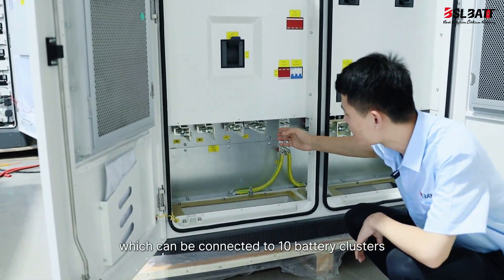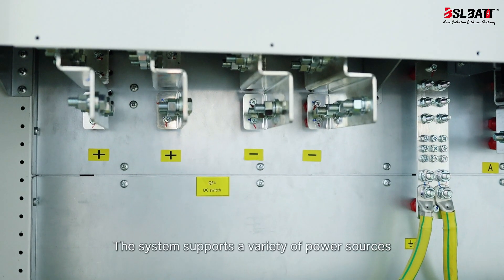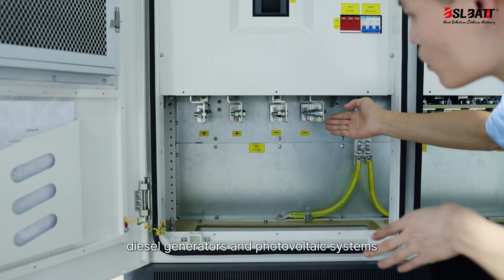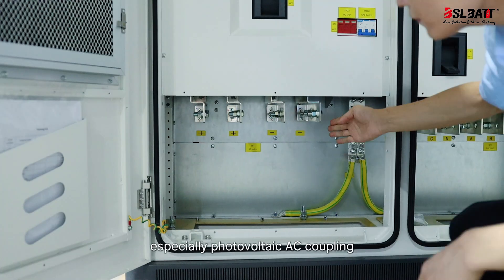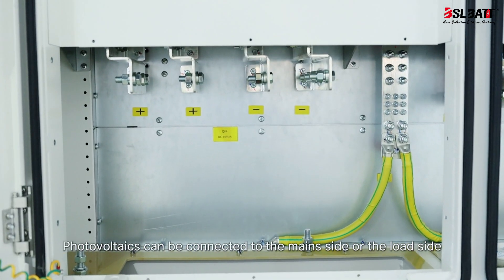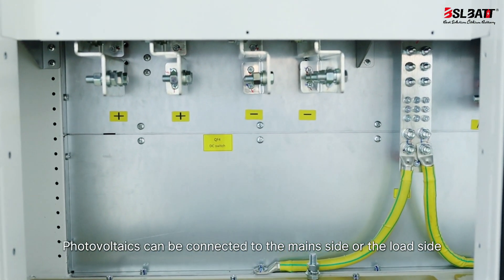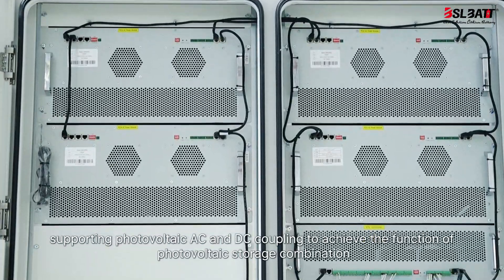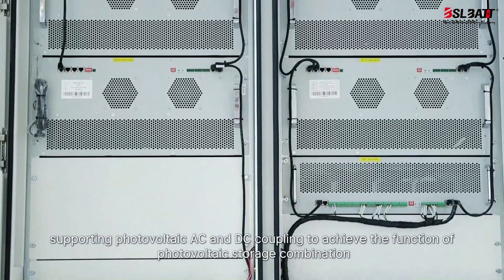The STS module in the cabinet has a power of 600 kW. Compared with the traditional ATS, it can switch on and off the grid faster. The PCS cabinet also integrates the function of the combiner box, which can be connected to 10 battery clusters. The system supports a variety of power sources including mains, diesel generators, and photovoltaic systems, especially photovoltaic AC coupling. Photovoltaics can be connected to the mains side or the load side, supporting AC and DC coupling to achieve photovoltaic-storage combination.